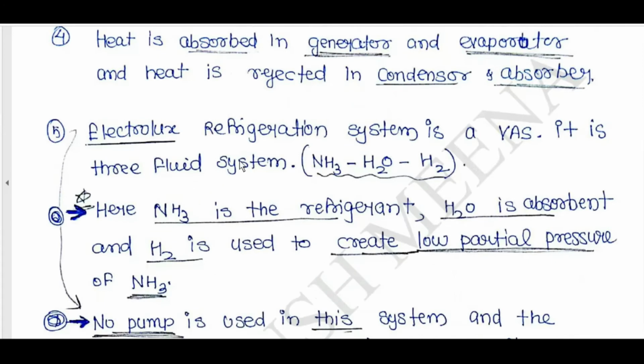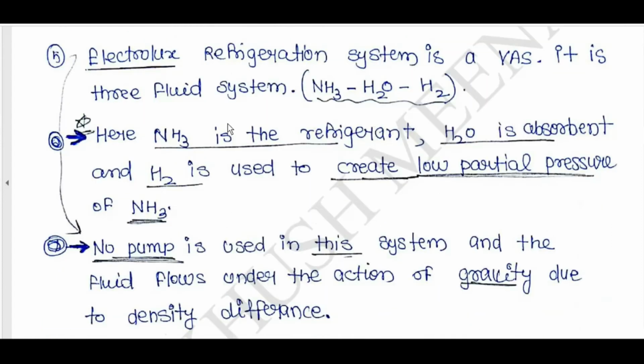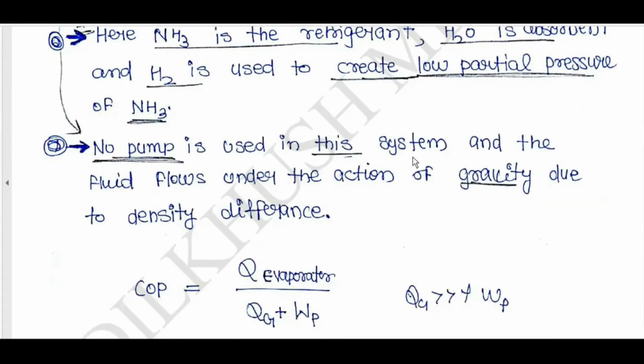The Electrolux refrigeration system is a VAS. It has three fluids: NH3, H2O, and H2. Here NH3 is the refrigerant, H2O is the absorbent, and H2 is used to create low partial pressure of NH3. No pump is used in this system, and the fluid flows under the action of gravity due to density difference.